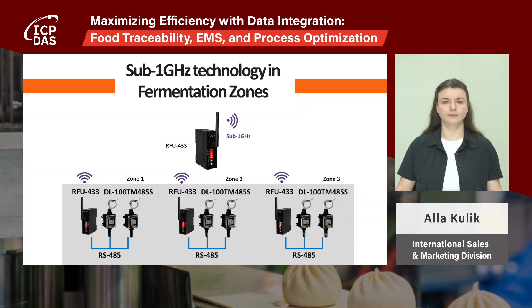The RFU433 is a reliable wireless communication module that converts RS-232/485 signals for long-range transmission, reaching distances up to 500 meters in the 433 MHz frequency band, designed for easy setup and robust performance in industrial environments. It includes DIP switch configuration for quick network organization, supporting 16 RF channels and 8 group IDs. Operating in the sub-G frequency range, the RFU433 avoids interference from commonly congested 2.4 GHz and 5 GHz bands, making it ideal for factory applications running stable wireless RS-232/485 communication.